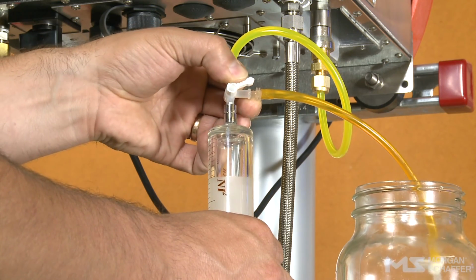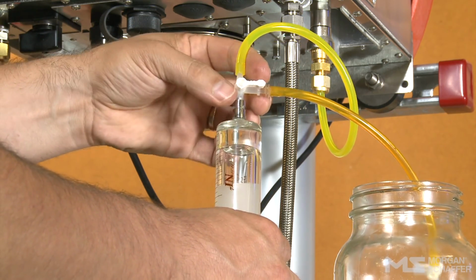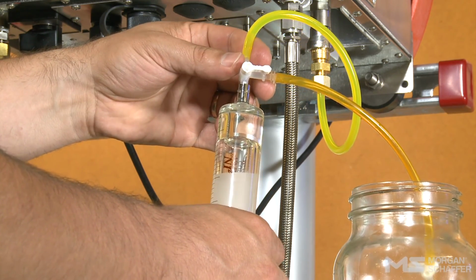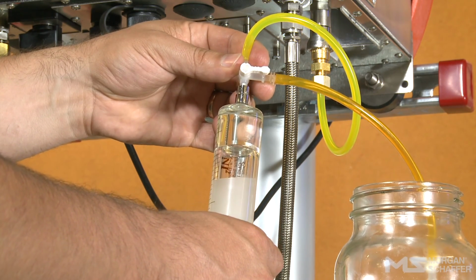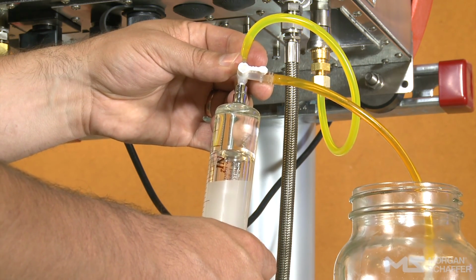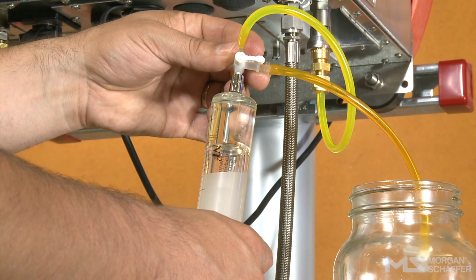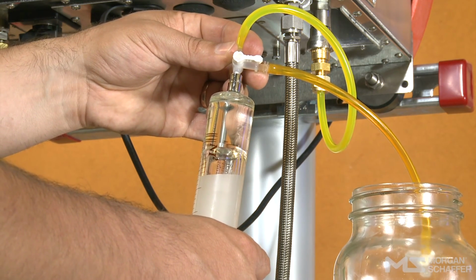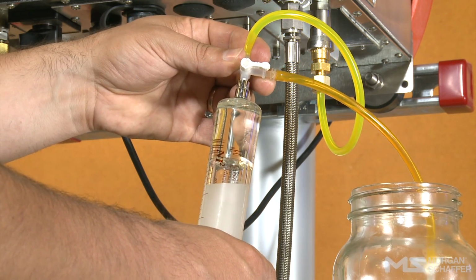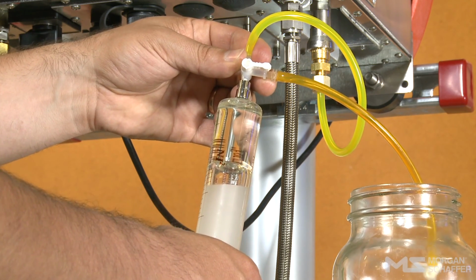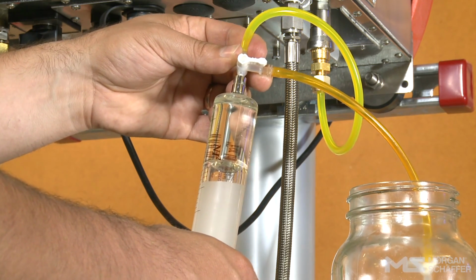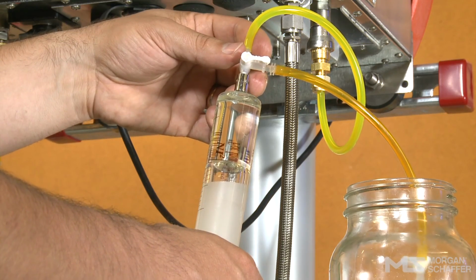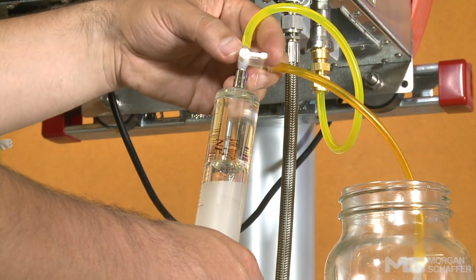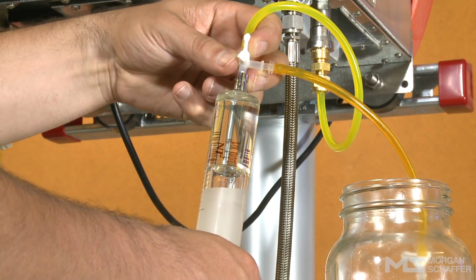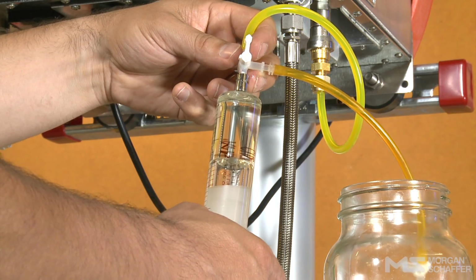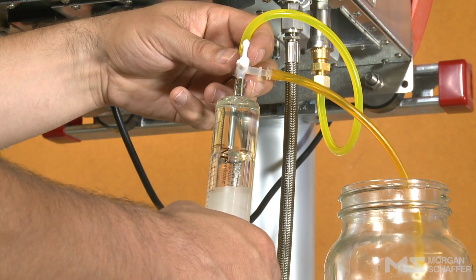Turn the 3-way stopcock handle toward the side port and allow the pressure inside the Calisto to fill the syringe with at least 30 cc's of oil. Do not pull on the piston to fill the syringe. Turn the 3-way stopcock toward the sampling tube and flush the contents of the syringe.